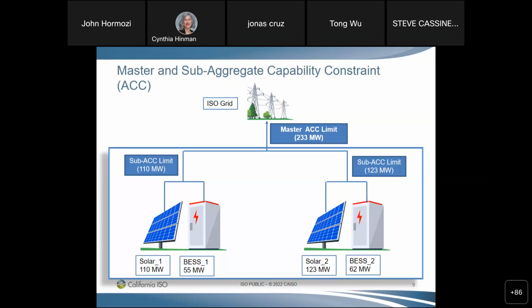The market will look at each resource individually. However, the master ACC constraint will limit the production to 233 megawatts, just like it does today. In addition, the sub-ACC for the resource on the left will limit their production to 110 megawatts, and the second sub-ACC on the right will limit those 2 resources to 123 megawatts. The master ACC limits the combined output of all 4 resources to no more than the studied interconnection of 233 megawatts, and the subordinates represent those contractual limitations I mentioned.